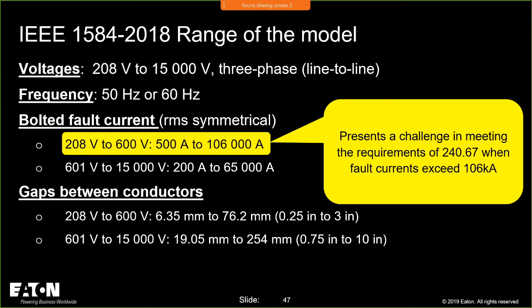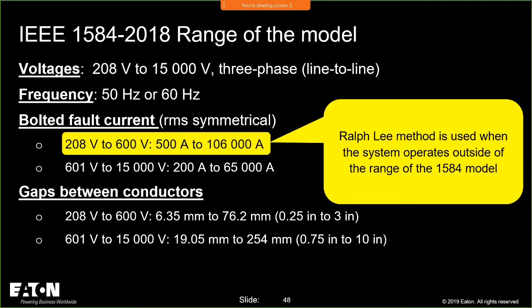That presents a challenge in 240.67, which I'm going to hopefully help you understand. The way that your SKM systems analysis studies and other similar ones, even 70E, recognize the Ralph Lee model, and 1584 recognizes that Ralph Lee model. So most of your studies will reference the Ralph Lee model, but the Ralph Lee model does not calculate arcing currents. What it does is take the three-phase bolted fault current, compare it with the clearing time of the fuse or breaker at that three-phase bolted fault current, and then it has an equation to calculate incident energy.